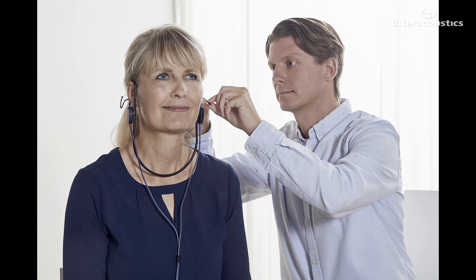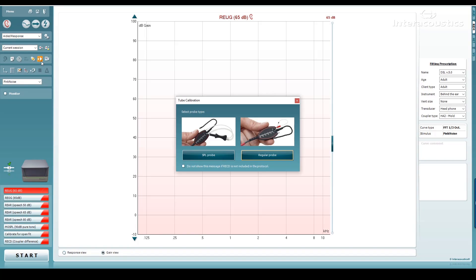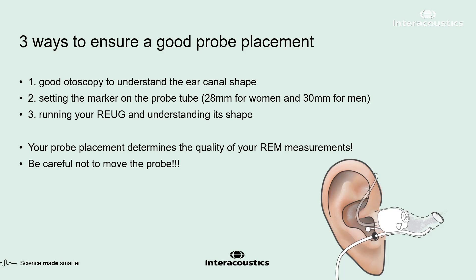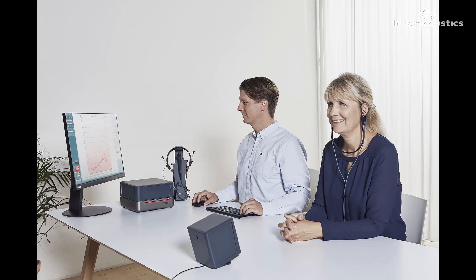Your probe tube is your measurement reference point for your fitting, and correct placement ensures quality measurements. Ahead of placement, run the tube calibration process to ensure your equipment is correctly prepared. You should follow these steps to ensure good probe tube placement: first, perform good otoscopy — ensure you know the shape of the patient's ear canal and observe for any obstacles. You can also perform otoscopy once the tube has been placed to get a better placement after readjustment. Second, move your marker on your probe tube to 28 or 30 millimetres depending on the patient's gender, to ensure you aren't over-inserting the probe. Finally, once the probe is placed, observe your REUG to assess probe placement quality. If you're not within 5 dB of the 0 dB mark at 6 kHz, reassess your probe tube placement.